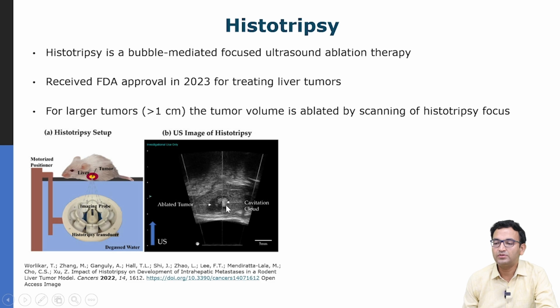Now, the beams are very sharply focused here. So, if the tumors are large in size, then the tumor volume is actually ablated by scanning the histotripsy focus mechanically. And here is an example image where you can see you have an array of histotripsy transducers. So, each of these structures is a separate transducer, and this array can actually be controlled with each element controlled individually, and in the center there is an imaging probe for image guidance, because you would like to see where you are shooting your signal, your therapy pulse, and you would like to passively receive the signal from there, as well as you would like to make an image of the region so that you can target your pulse.